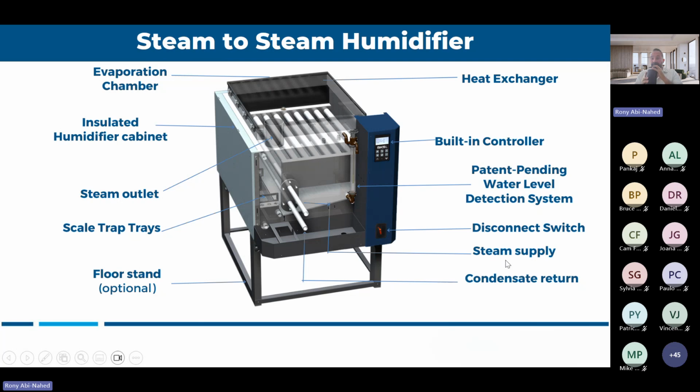The third option you have is the steam to steam. Usually we used to sell a lot of those in hospitals because hospitals always have boilers. But in the past years, boilers had a lot of chemicals inside of them, and you don't want to inject these chemicals directly into the space.